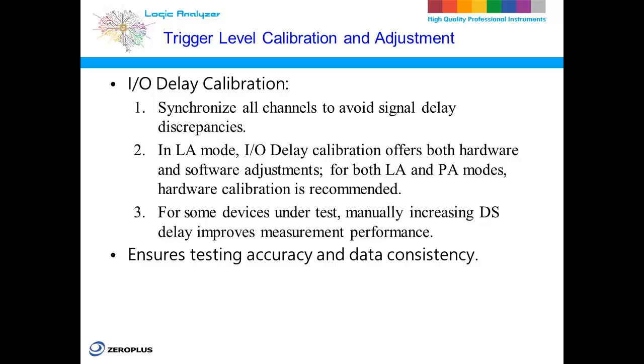In LA mode, there are two methods for I/O delay calibration: hardware calibration and software correction. We highly recommend using hardware calibration in both LA and PA modes because it provides more precise synchronization and helps minimize errors caused by hardware delays. Hardware calibration adjusts the hardware settings of the measurement system to minimize delays between all channels. This is especially important for capturing high-frequency or fast signals, because even small delays can have a significant impact on the accuracy of the signal.